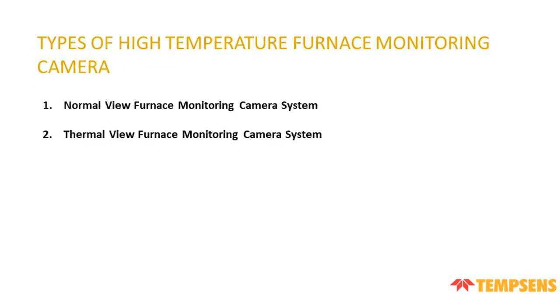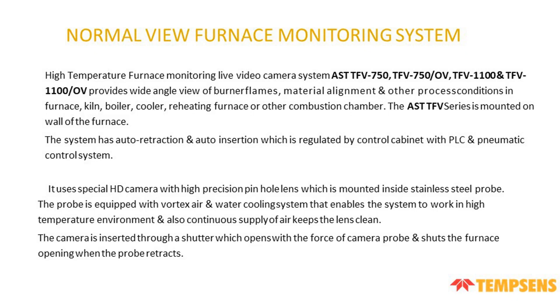Types of high temperature furnace monitoring camera: normal view furnace monitoring camera system and thermal view furnace monitoring camera system. Normal view furnace monitoring system. High temperature furnace monitoring live video camera system AST TFV-750, TFV-750/OV, TFV-1100 and TFV-1100/OV provide a wide angle view of burner flames, material alignment and other process conditions in furnace, kiln, boiler, cooler, reheating furnace and other combustion chambers. The AST TFV series is mounted on a wall of the furnace.